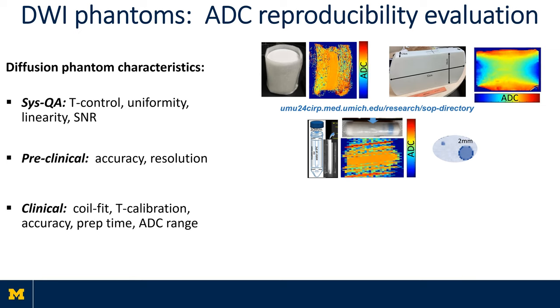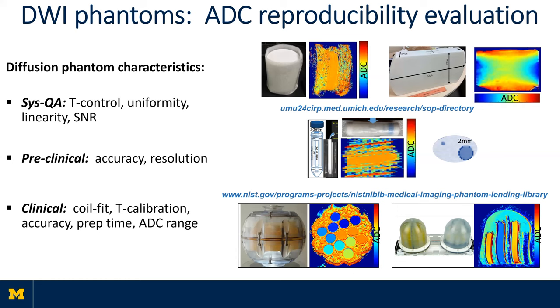For preclinical scanners, the same materials can be utilized to provide accurate ground truth ADC, and the challenge shifts to testing resolution and partial volume representative of minute animal body habitus, for instance 2 millimeters versus half a millimeter for mouse tibia. For phantom use in a clinical environment, time-saving and easy preparation become important, and the range of ADC values is designed for scanning at ambient temperature. This necessitates temperature monitoring and calibration for specific phantom materials. Furthermore, permanent phantom housing has to fit specific imaging coils, like the NIST polyvinyl pyrrolidone phantom for head and breast coils, which increases overall phantom cost.